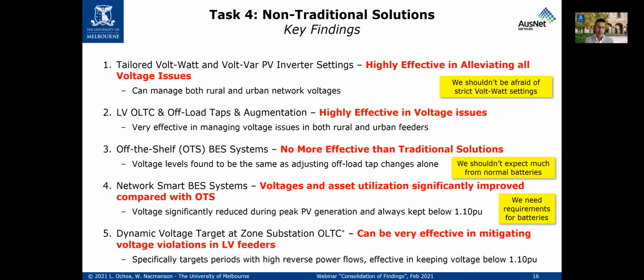Then investigating the use of low voltage on-load tap changers, a technology that already exists and is commercially available but still not used widely—very effective, of course combined with augmentation, and combined with offload tap changers when needed, because you don't always need the on-load tap changers at low voltage. Very effective in managing voltage, definitely, and when you combine anything with augmentation, you cover everything—congestion and voltage problems.